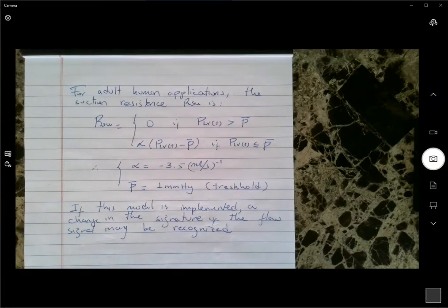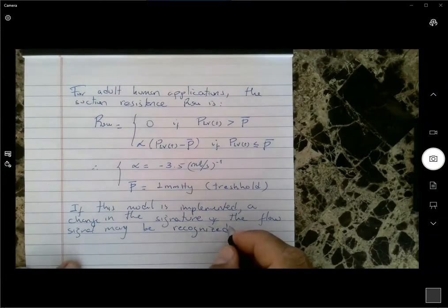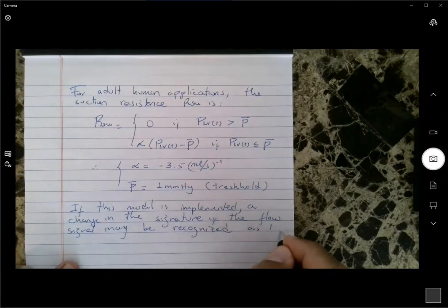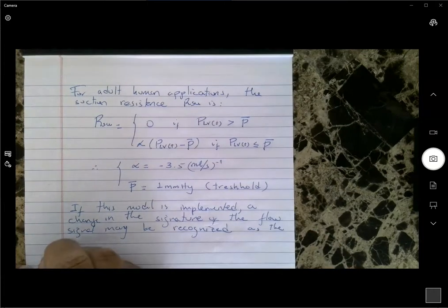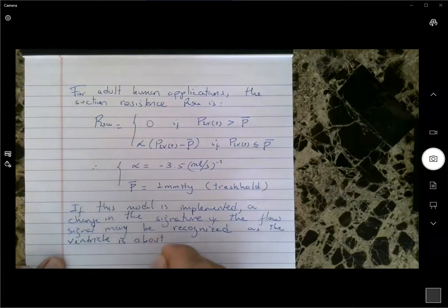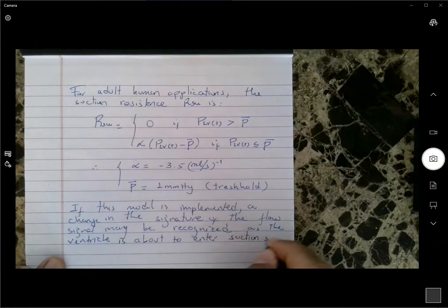So you can use some pattern recognition type algorithms to determine when this happens, and then tell the pump flow—you can incorporate this into the active feedback control loop and say, okay, if I recognize this particular signature, go on and slow down the pump because you're about to enter suction. So maybe recognize that the ventricle is about to enter a suction state.